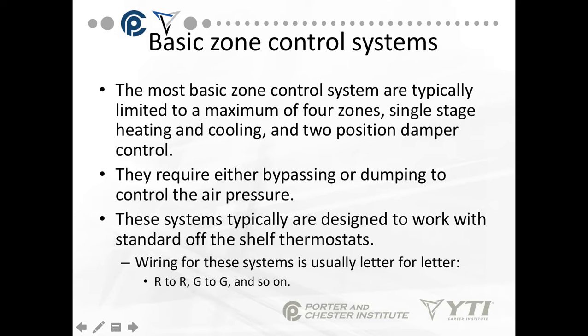The basic control system is usually limited to a maximum of four zones, single-stage heating and cooling, and two-position damper control. In other words, the damper is either open or closed. They require either bypassing or dumping to control the air pressure. The systems are designed to work with standard off-the-shelf thermostats.